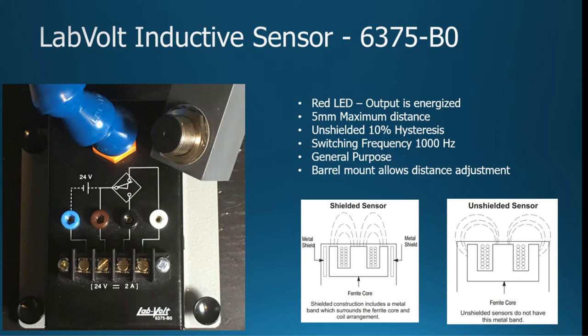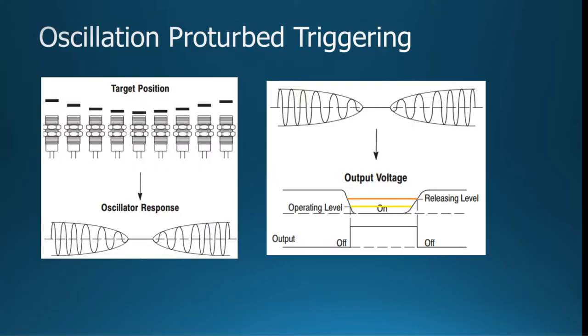This is just a general purpose. It's barrel mounted, allows the distance change there. So what will happen is in that five millimeter distance, as your target moves closer and starts perturbing that space, there's an oscillating response to that change in that magnetic field. As that field gets kind of pushed down because a piece of metal gets into it and affects the magnetic field that was currently being generated, it will go through and trigger.